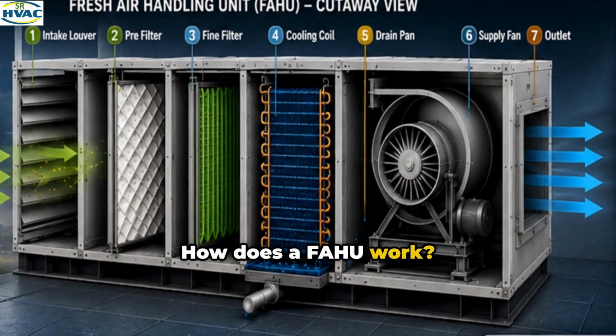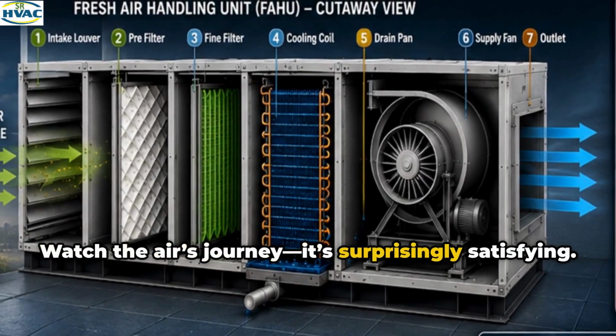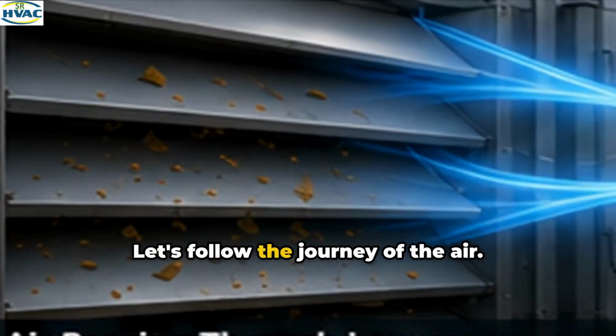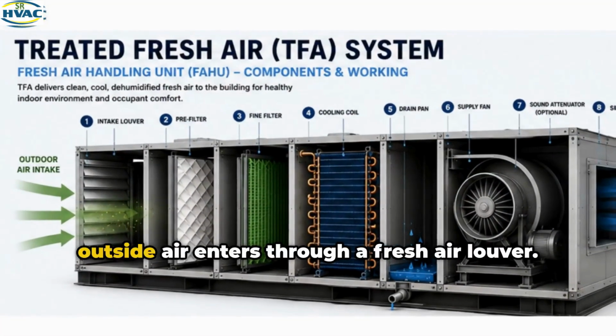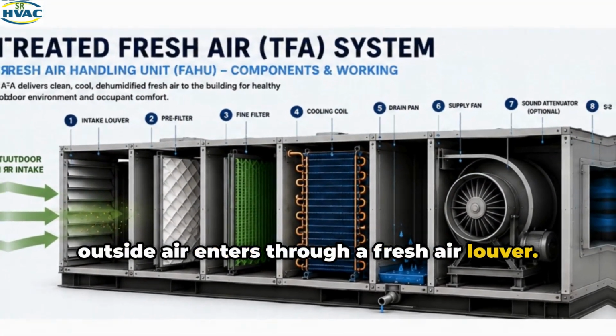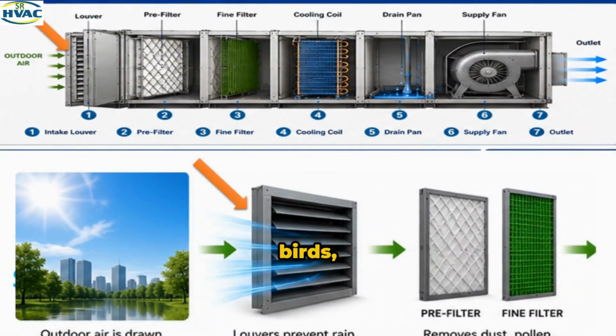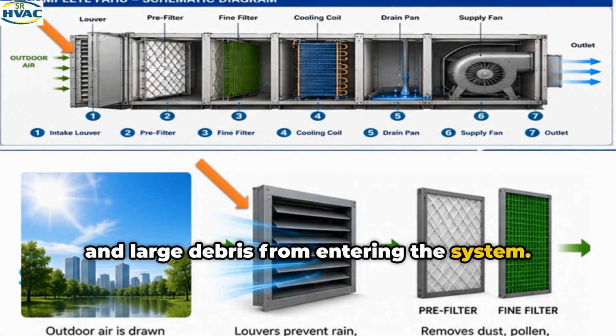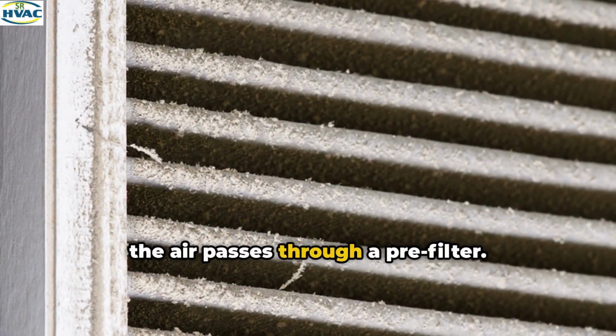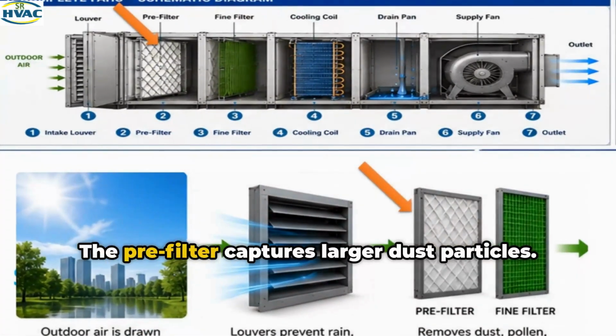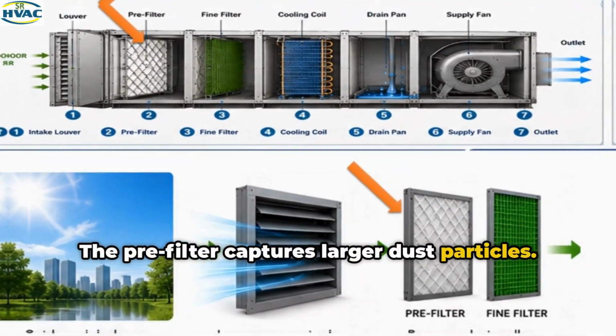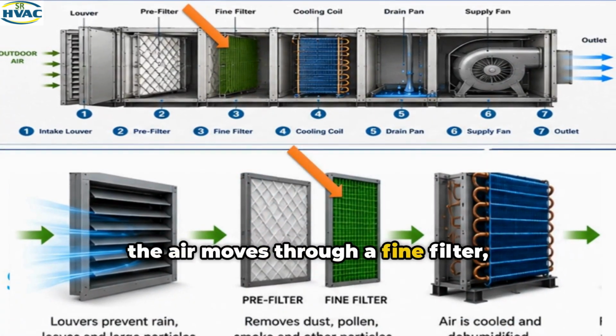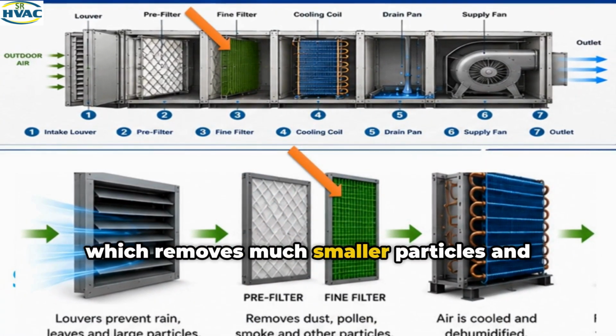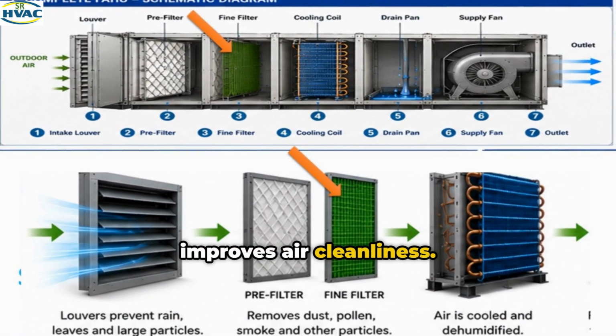How does a FAHU work? What's the air's journey? It's surprisingly satisfying. Let's follow the journey of the air. First, outside air enters through a fresh air louver. This louver prevents rain, birds and large debris from entering the system. Next, the air passes through a pre-filter. The pre-filter captures larger dust particles. After that, the air moves through a fine filter which removes much smaller particles and improves air cleanliness.